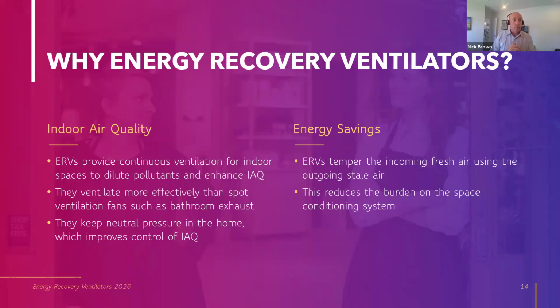The energy savings piece comes because ERVs are pulling in outdoor air, but they're tempering that incoming fresh air using the outgoing stale air stream. The streams never cross, never exchange pollutants, but they're allowed to exchange heat. We've got a slide coming up showing some example temperatures to give you that idea. But that's where the energy savings comes from.